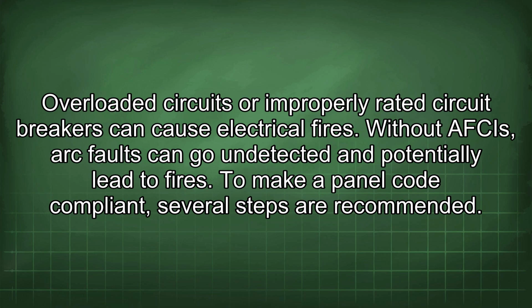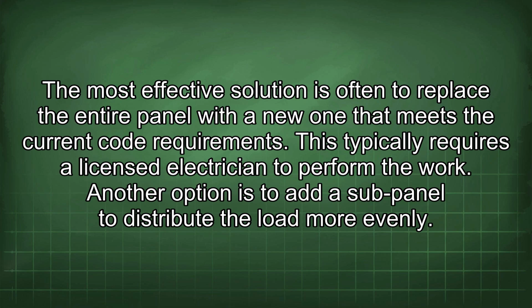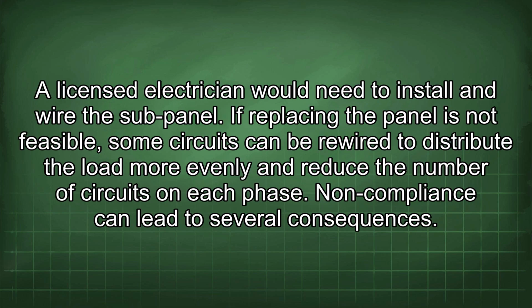To make a panel code compliant, several steps are recommended. The most effective solution is often to replace the entire panel with a new one that meets the current code requirements. This typically requires a licensed electrician to perform the work. Another option is to add a sub-panel to distribute the load more evenly. A licensed electrician would need to install and wire the sub-panel. If replacing the panel is not feasible, some circuits can be rewired to distribute the load more evenly and reduce the number of circuits on each phase.